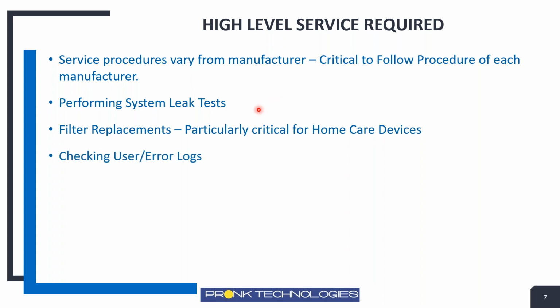So these things, of course, are critical to always make sure we're maintaining and replacing at the proper intervals. Checking the user error logs in the ventilators can be a great tool to make sure we're able to identify any possible errors that are occurring. Of course, if there's a patient incident, the error logs are one of the first places you go look to try to understand what could have occurred and do your analysis to trace back what could have caused the problem with that device. So making sure we're taking advantage of the information there can be important.